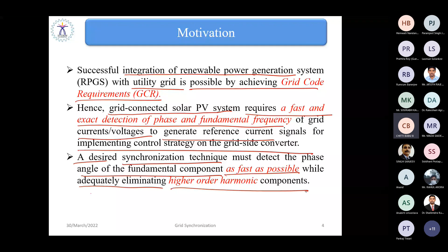So a desired grid synchronization technique must detect the phase angle of the fundamental component as fast as possible while adequately eliminating higher order harmonic components. Because invariably, the inverter injects high frequency harmonic components due to non-uniform sampling frequency or non-uniform inverter switching. So while proposing any kind of grid synchronization technique for estimating the fundamental frequency, basically it acts as a filter to filter out unwanted harmonic presence in the inverter output current or inverter output voltages.